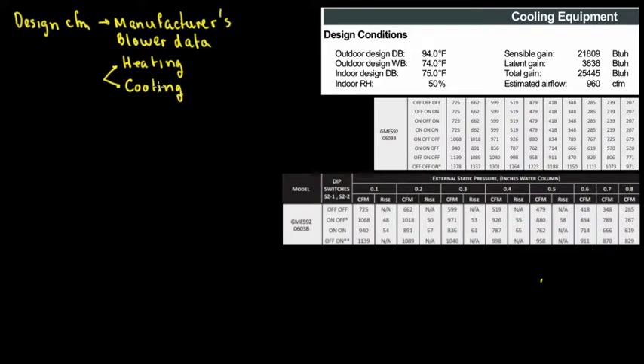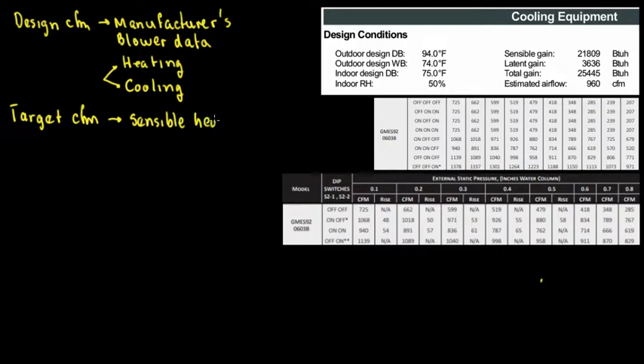So how do you get a baseline or guideline on what the CFM would be? That's what we call the target CFM. The target CFM is what you are trying to accomplish, and it is based on the sensible heat equation. The target CFM uses the sensible heat equation to find out what the CFM would be for a proper heat load.